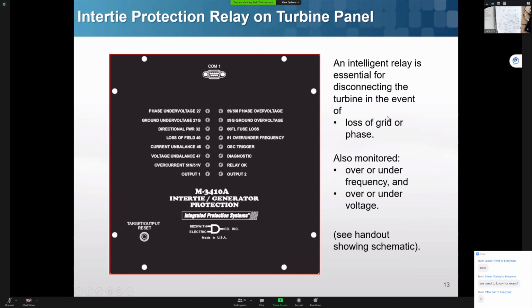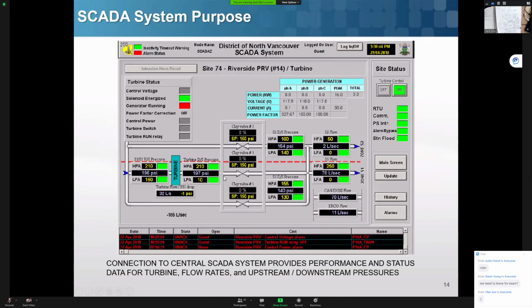So they will have a type of protection if you lose the grid or phase, and monitor over and under frequency and over and under voltage. This is the picture of the SCADA system. So they will monitor the voltage at the different phases and the current at the different phases, and the power or power factor, and they also monitor the pressure in the turbine, you can see here.